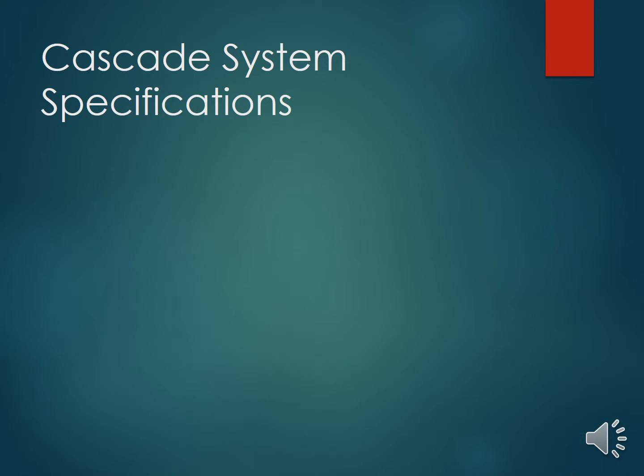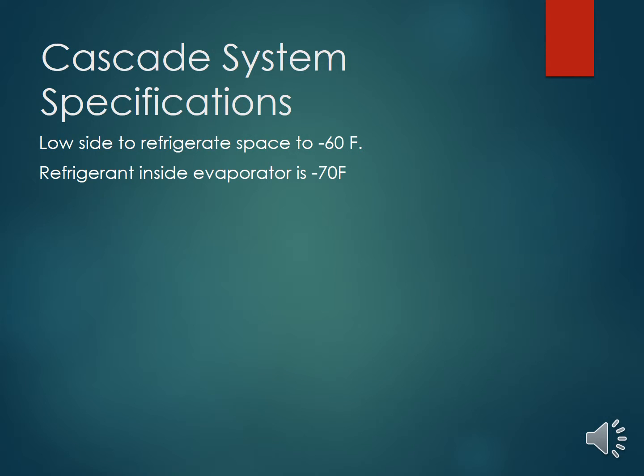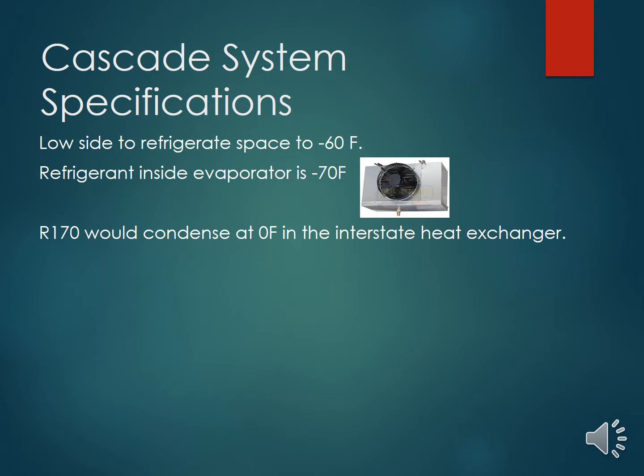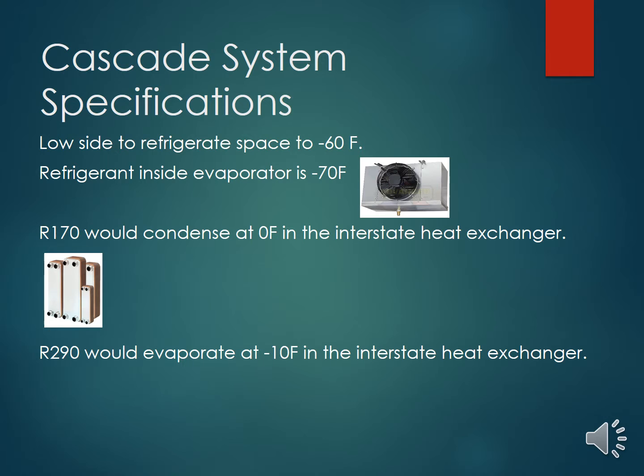Calculations predict that the airspace within the refrigerated space will achieve minus 60 degrees Fahrenheit. This is caused by the R170 evaporating at minus 70 degrees Fahrenheit. Calculations also predict that once the R170 is compressed, it will condense at 0 degrees Fahrenheit within the interstage heat exchanger. Likewise, the R290 will evaporate at minus 10 degrees Fahrenheit within the interstage heat exchanger. After compression, the R290 will condense at 95 degrees Fahrenheit.